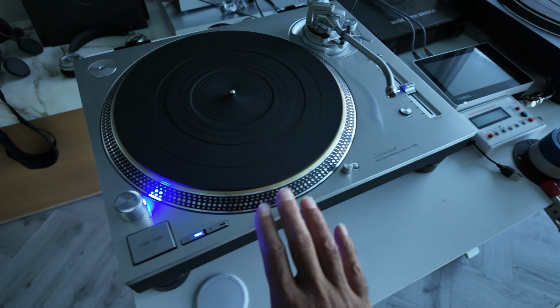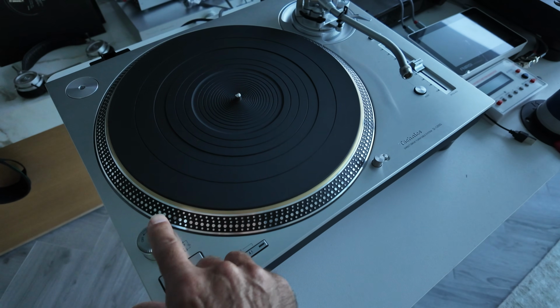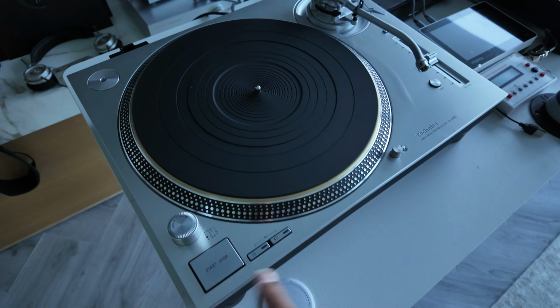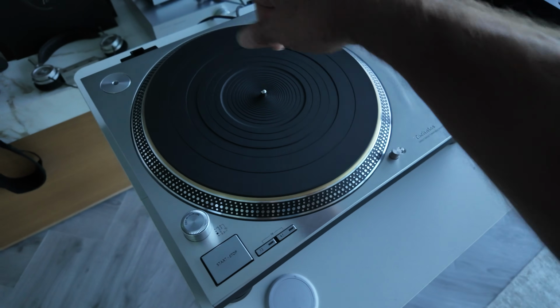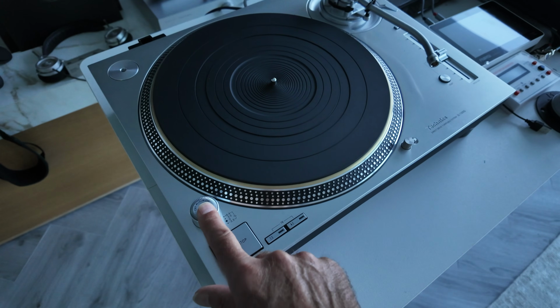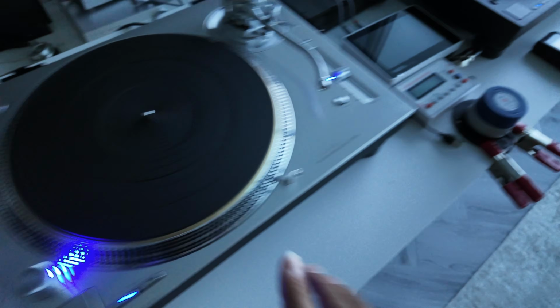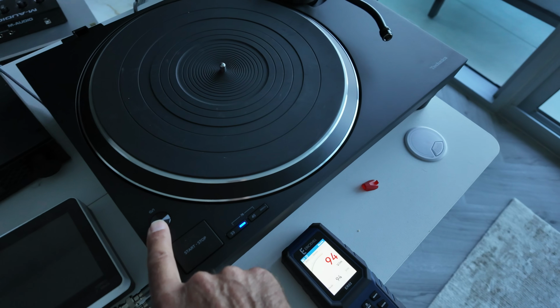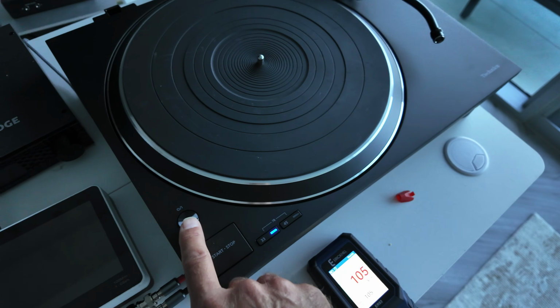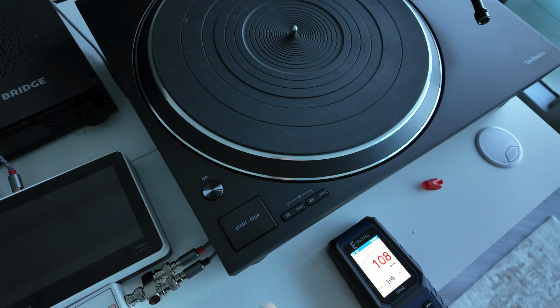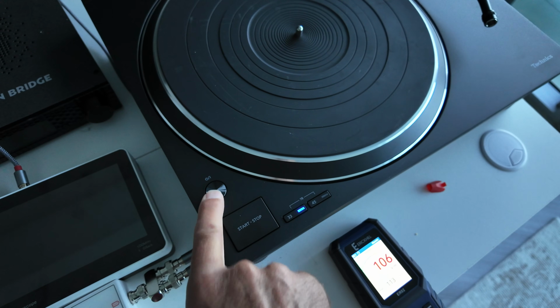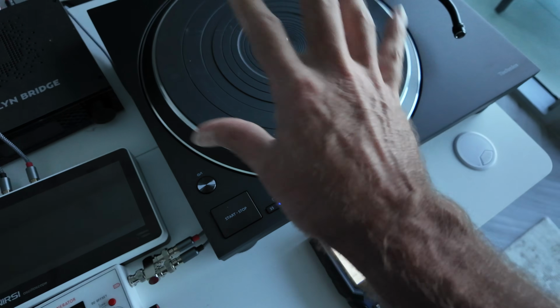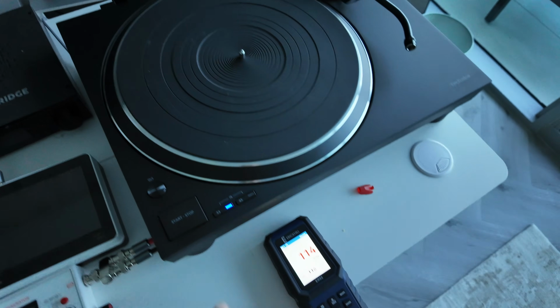I've noticed another thing on the 1200 is that the power button is a true power button. I'm almost certain the power comes in through the power switch, so it's actually completely off at this point. While on the 1500C, it probably uses some sort of regulated power supply that just goes into standby mode, because there is some residual noise on there - it's just always waiting, some residual voltage within the power supply.